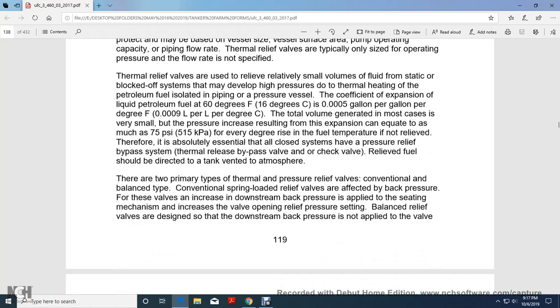The thermal relief valves are used to relieve a relatively small volume of the fluid for the blocked-up systems that develop high pressure from thermal heating of the petroleum isolated within the piping or the pressure vessel. With the coefficient of expansion of the liquid petroleum at 60 degrees, a very small volume increase results in as much as 75 psi for every degree rise in fuel temperature if it is not relieved. Therefore, it is absolutely essential that all closed systems and pressure relief systems have a thermal bypass valve with a check valve. Relieved fuel should be directed to the tank, not vented into the atmosphere.